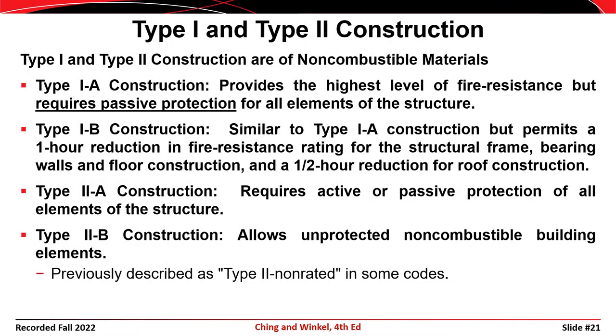Construction Type 1A provides the highest level of fire resistance and, as a result, the height of these structures is generally unlimited. But buildings in this class also require passive fire protection on all elements of the structure. Type 1B is similar to Type 1A, but less fire protection is permitted, resulting in a one-hour reduction in the fire resistance rating for most structural elements and a half-hour reduction for the roof. Type 2A construction requires active or passive protection for all elements of the structure, whereas Type 2B construction does not require fire protection for the structural elements. One of the key takeaways is that steel construction generally falls into one of these four classifications.